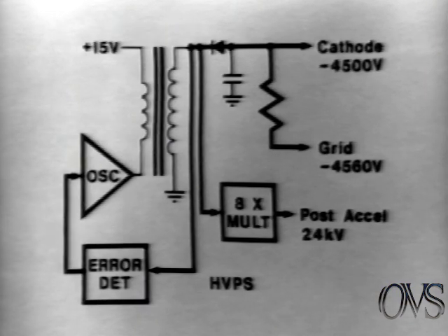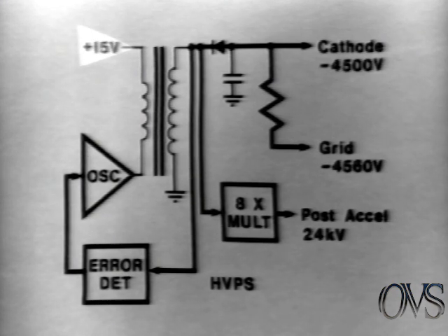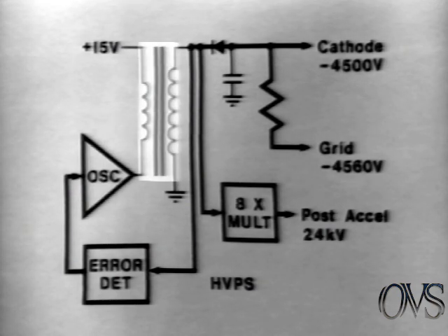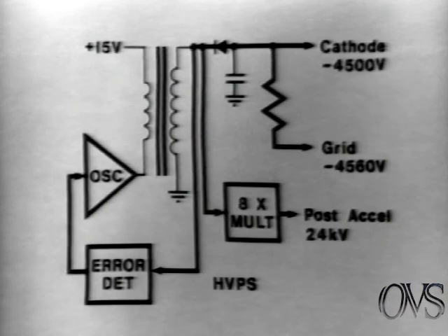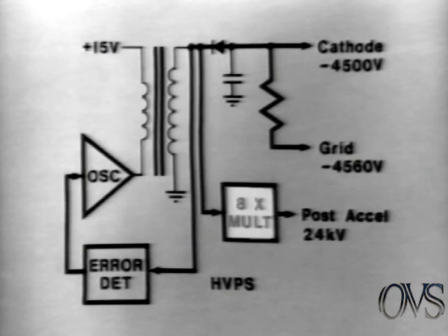The high voltage power supply provides the necessary voltages for the CRT. Plus 15 volts from the low voltage supply provides operating bias for an oscillator circuit, which drives a step-up transformer. The high voltage AC developed on the secondary winding is rectified, filtered, and applied to the CRT cathode and control grid. The high voltage AC is also applied to a voltage octupler, where it's rectified and multiplied by a factor of 8. The 24 kilovolt output is applied to the CRT post accelerator. The output level of the secondary winding is monitored by an error detector. If the voltage varies from normal, the detector provides a correction signal to the oscillator to change the primary voltage, compensating for the variations.